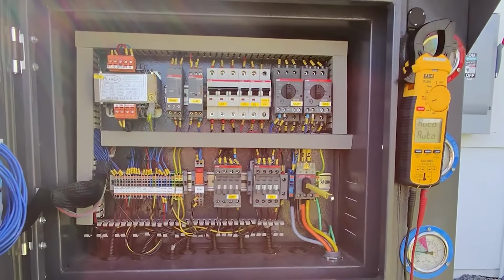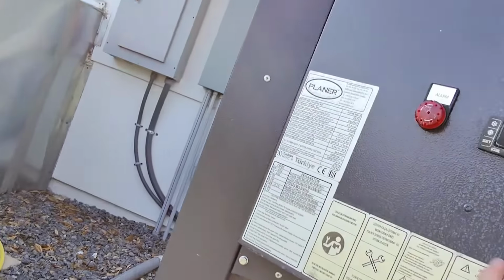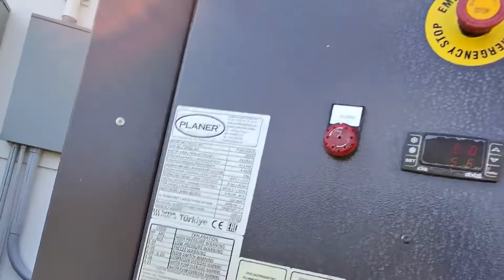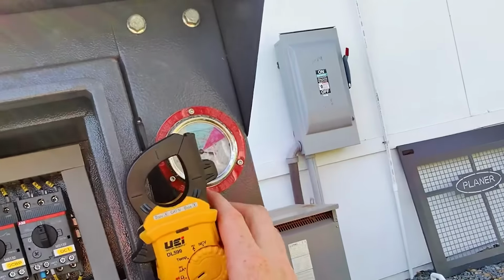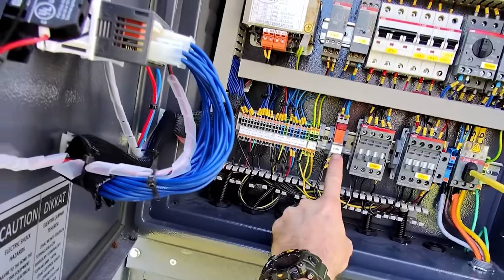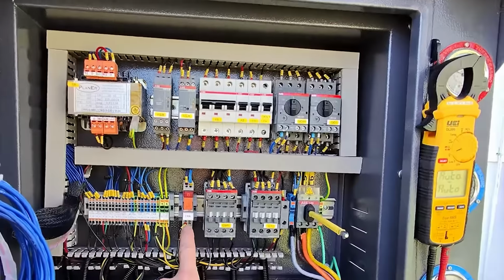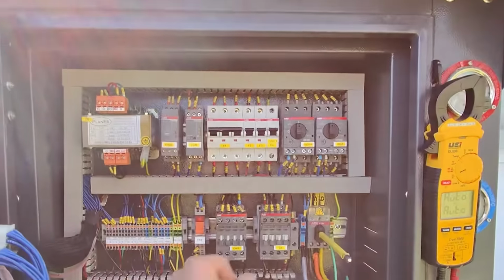So once I got that to clear, I was getting an A0 error code, which is a high pressure trip. Our PSI was getting all the way up to 650, then it would kick and I'd get the annoying buzzing sound. Come to find out that our fan ice cube relay was not energizing when it was getting a command signal, like it has right now, 50 volts.